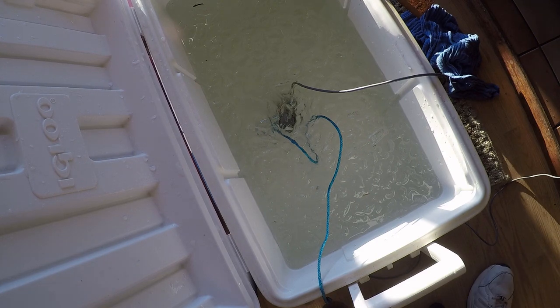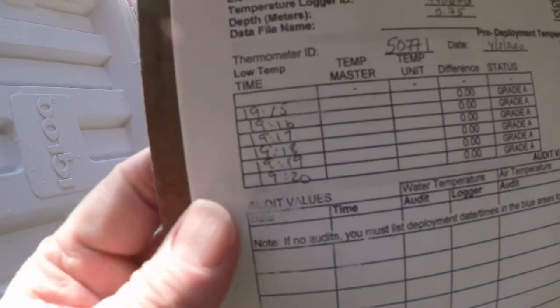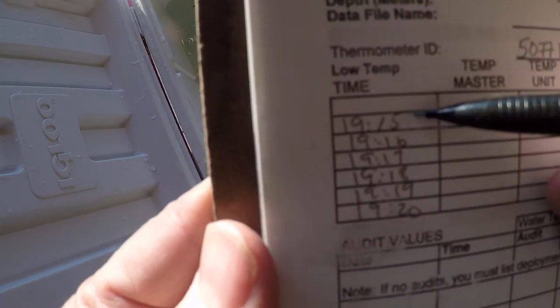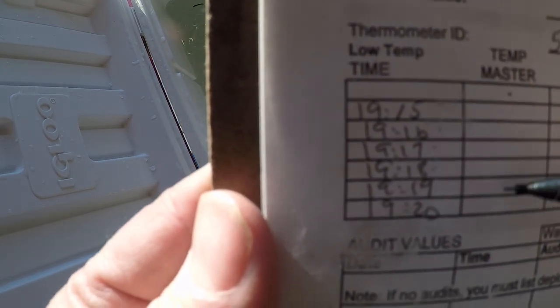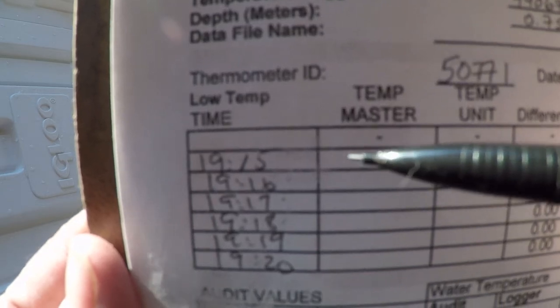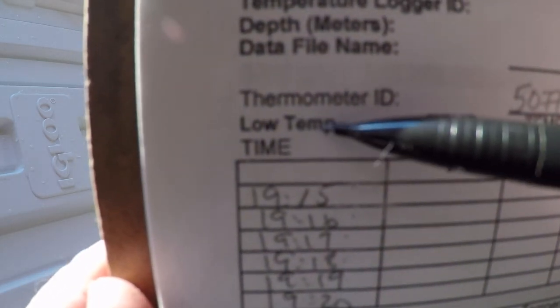Okay, so we've waited about 10 minutes for this. I've already filled out the times on here. We're going to do it at 1915, 1916, 17, 18, 19, and 20, and that will be our read times. Once again, we're going to put it under the master temperature unit, because that's what we're doing off of our NIST thermometer. This is the low temp one because we're doing it in the ice bath, and this is all under the pre-deployment temperatures.